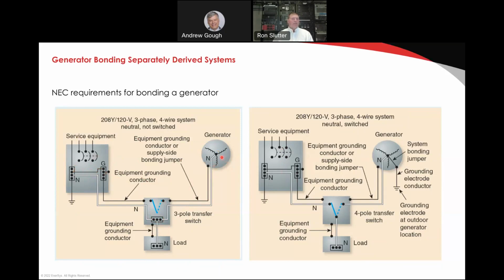Now, in a generator, if you're standard like this and you see a neutral ground bond in the generator, that's probably inaccurately installed. Why does that happen? It happens because every generator is shipped with the bonding equipment. So an electrician will find this screw or this jumper in the side of the circuit breaker cabinet, and he'll go, oh, I must have to install this. And so maybe 20% of the sites I go to, I find that this generator is neutral ground bonded. That can cause problems.